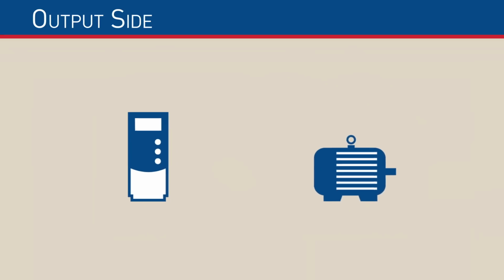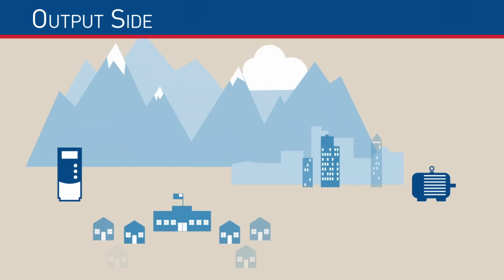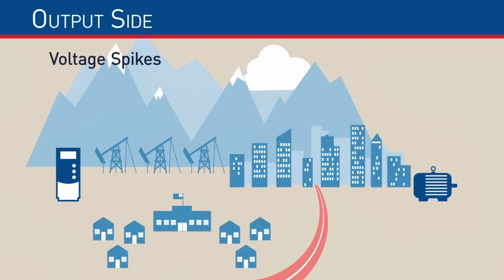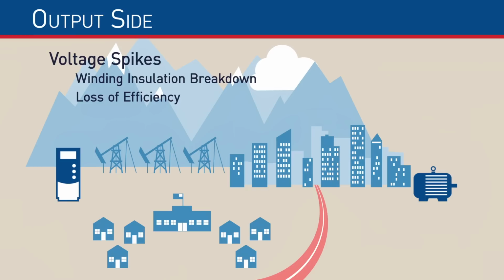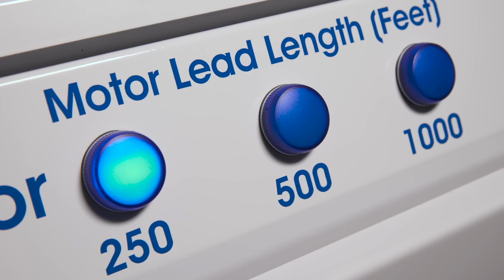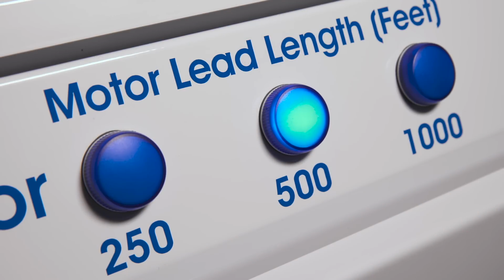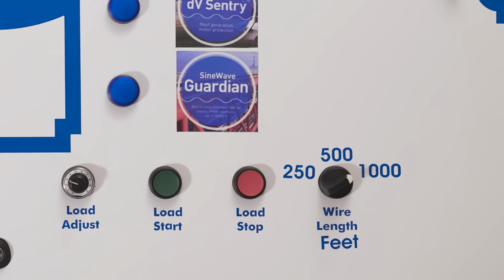Unfortunately, those pulses, when combined with long lead lengths, can result in voltage spikes at the motor, causing winding insulation breakdown, loss of efficiency, overheating, and bearing damage. Inside our demonstration unit, we have the capability of running 250, 500, or 1,000 feet of cable between the drive and motor. For the purpose of comparing MTE's motor protection solutions, we will run the system with 1,000 feet of cable and see what happens.